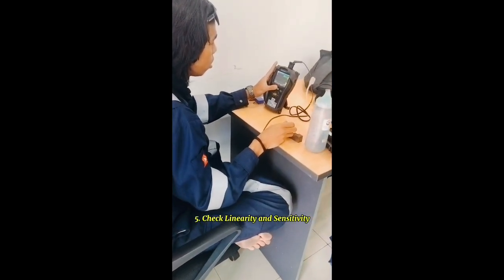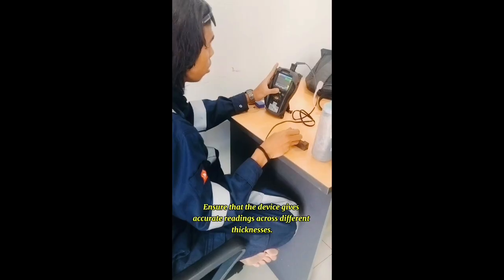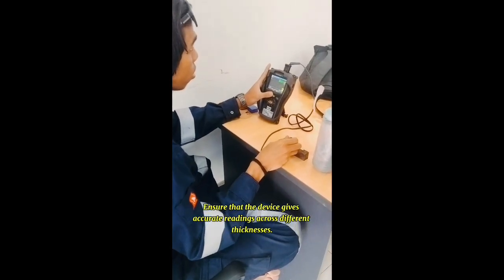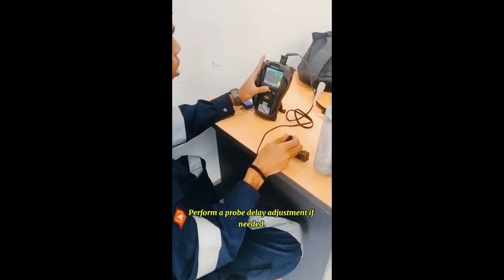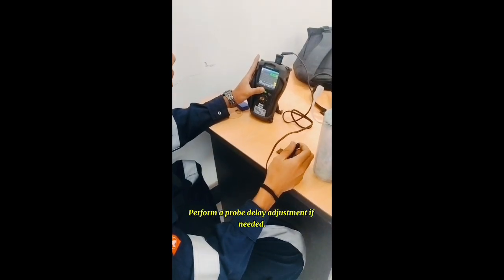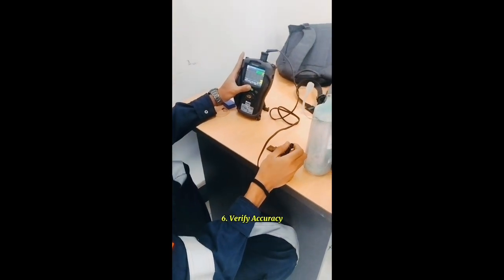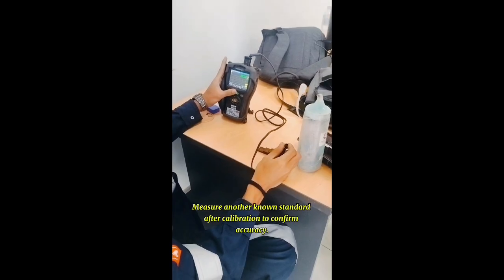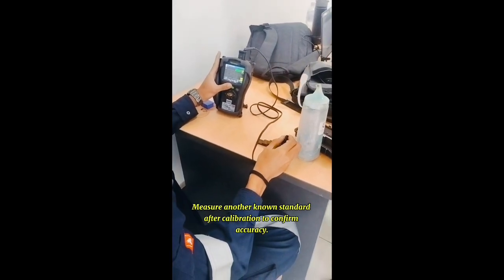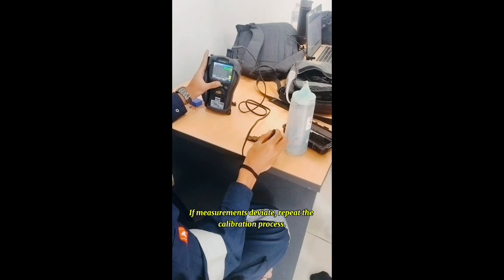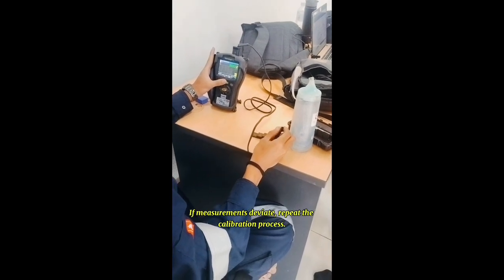5. Check linearity and sensitivity. Ensure that the device gives accurate readings across different thicknesses. Perform a probe delay adjustment if needed. 6. Verify accuracy. Measure another known standard after calibration to confirm accuracy. If measurements deviate, repeat the calibration process.